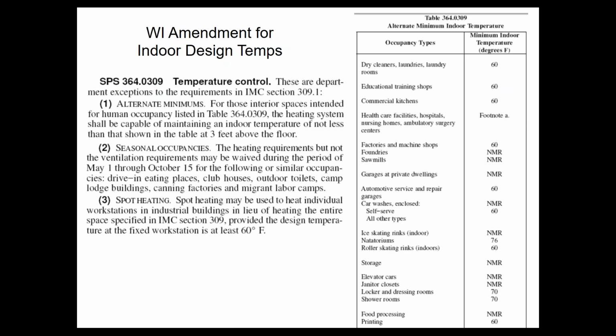On the indoor side, Wisconsin has an amendment commercially as well. Certain spaces do not have to do the 72 and 75. And if you look at the list of spaces down the right-hand side, they're ones that make sense. They're typically industrial type things and specialty areas. So you might not have to do the normal. You might have a different minimum heating temperature in those cases.